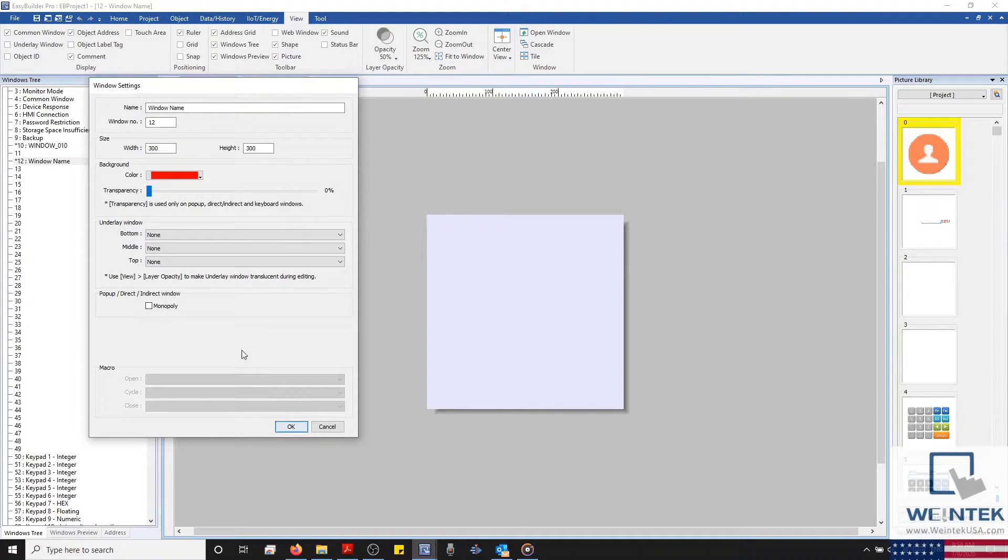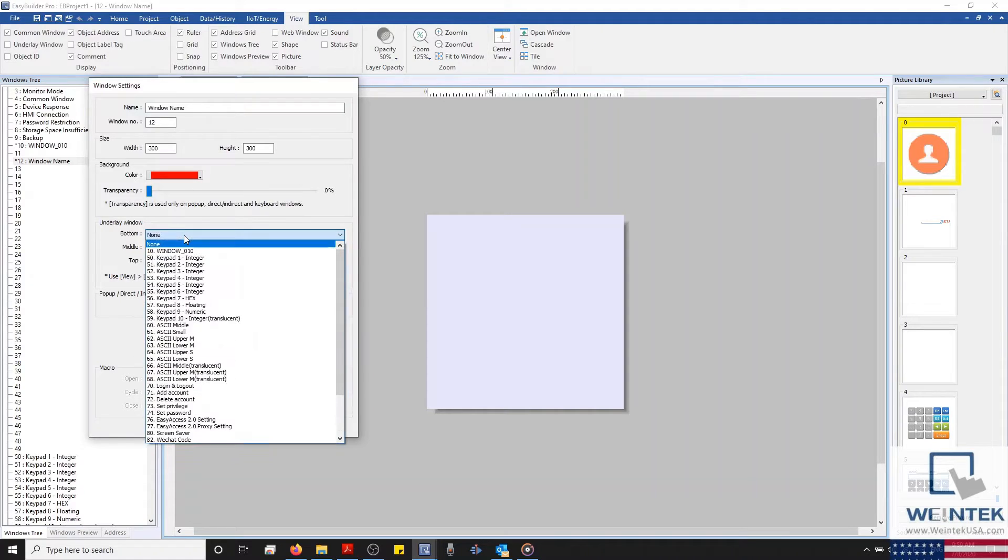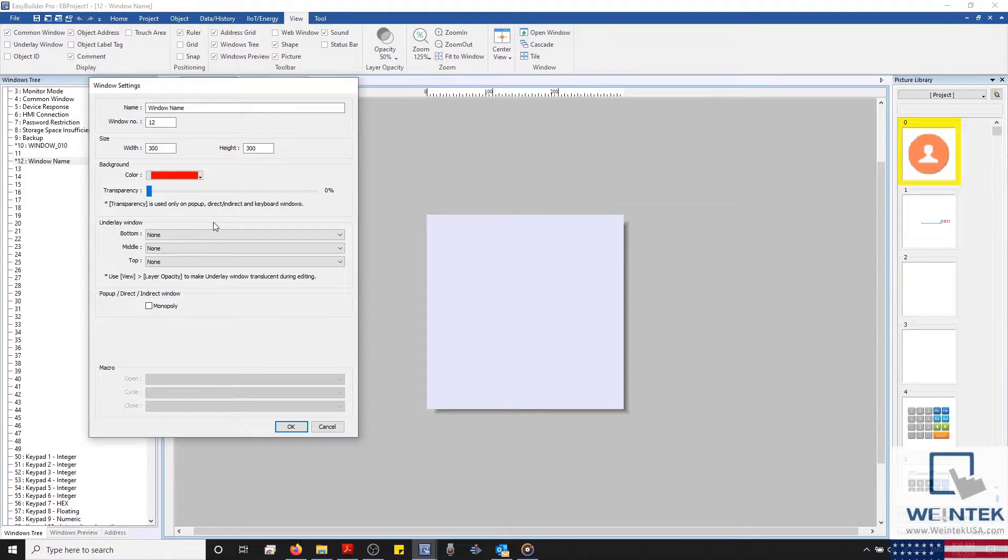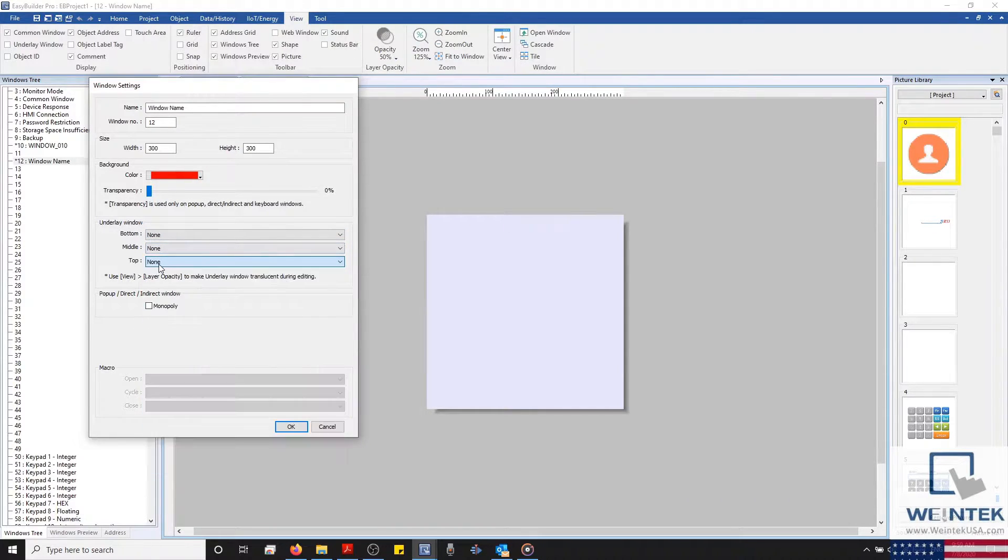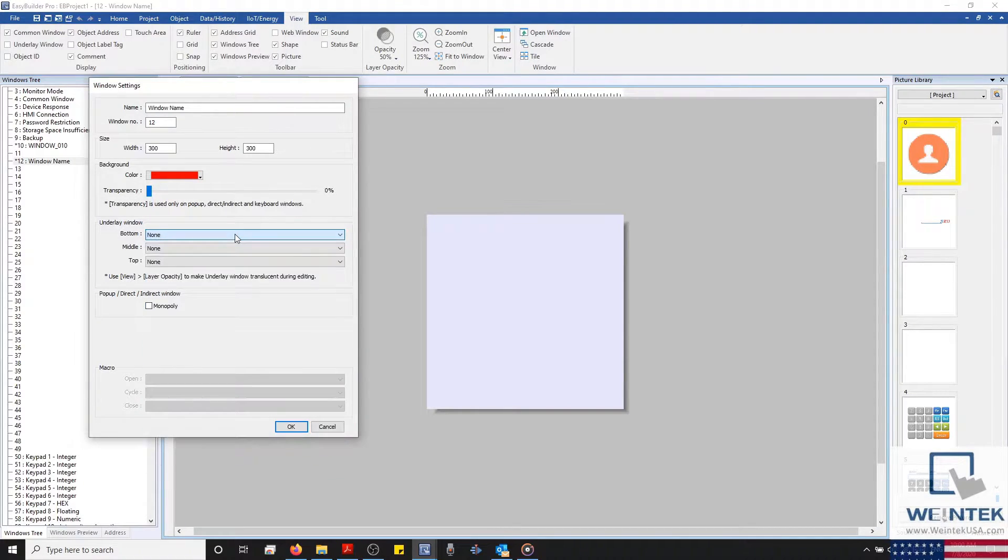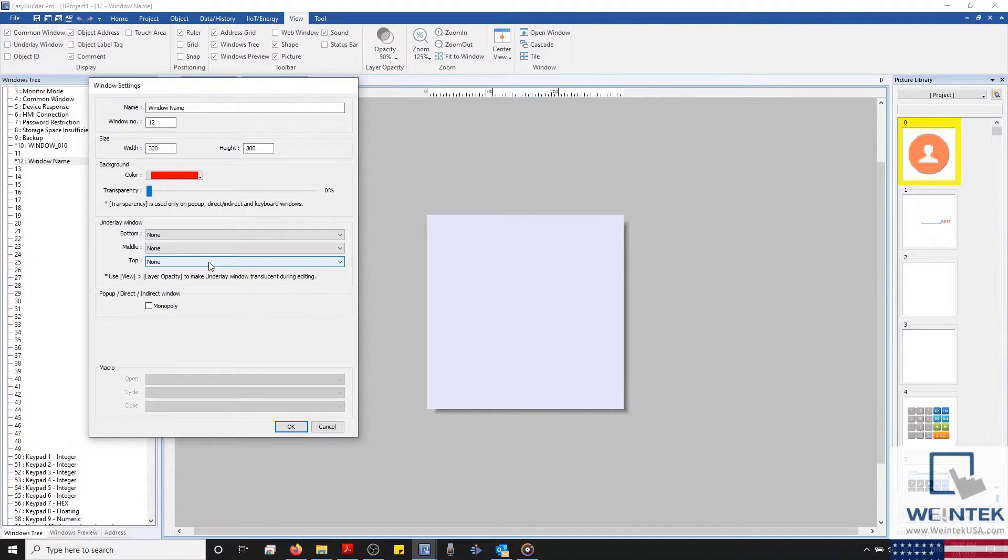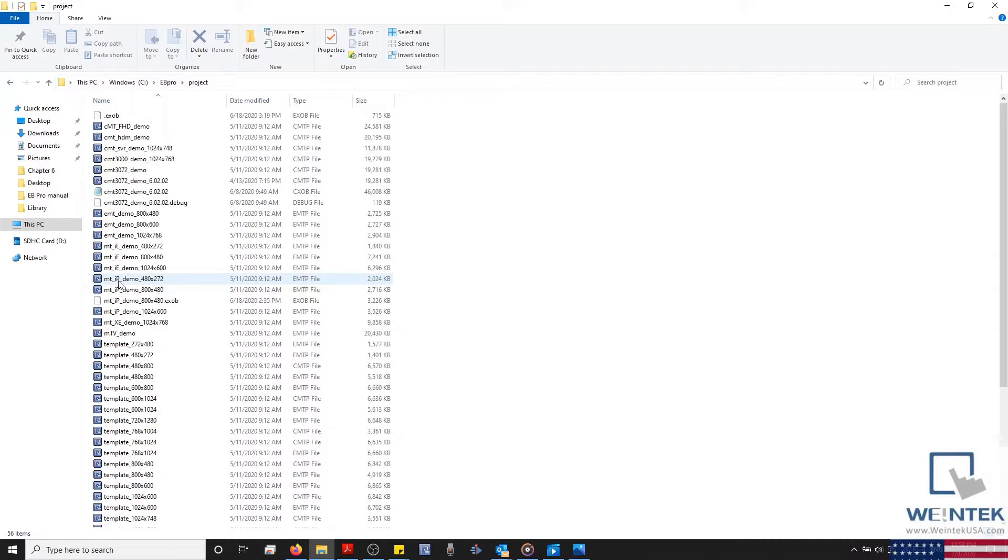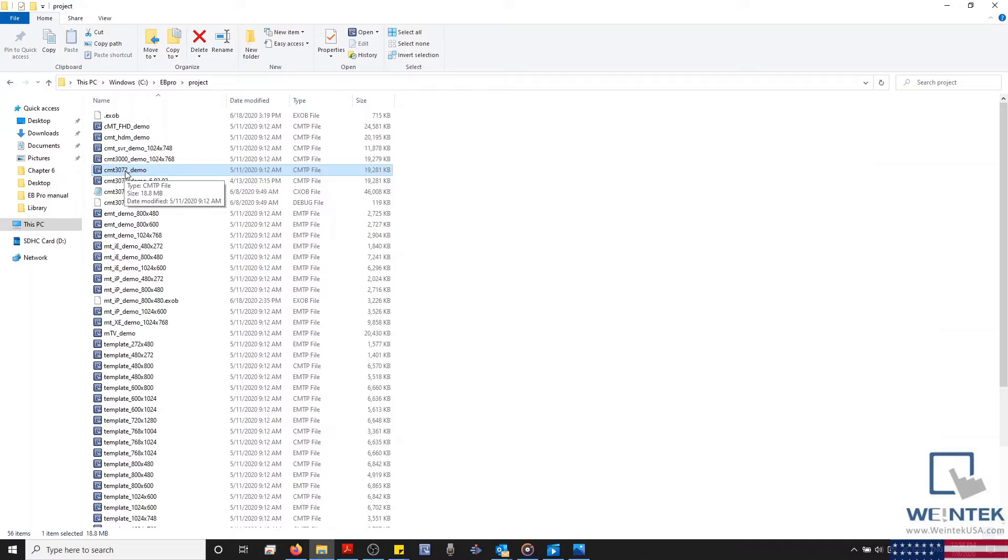And towards the center, we can define an underlay window. Underlay windows can be used to help give your project a custom background or reduce repetitive object creation. The bottom, middle, and top refer to the order in which the underlay windows are, in a sense, stacked, meaning that you have a general project background that is used as the bottom underlay window throughout your project. And certain screens might have different menus, and the menu can be configured as the middle or top layer. A great example of how best to use underlay windows can be found within the CMT demo project located within the installation directory of EasyBuilder Pro.